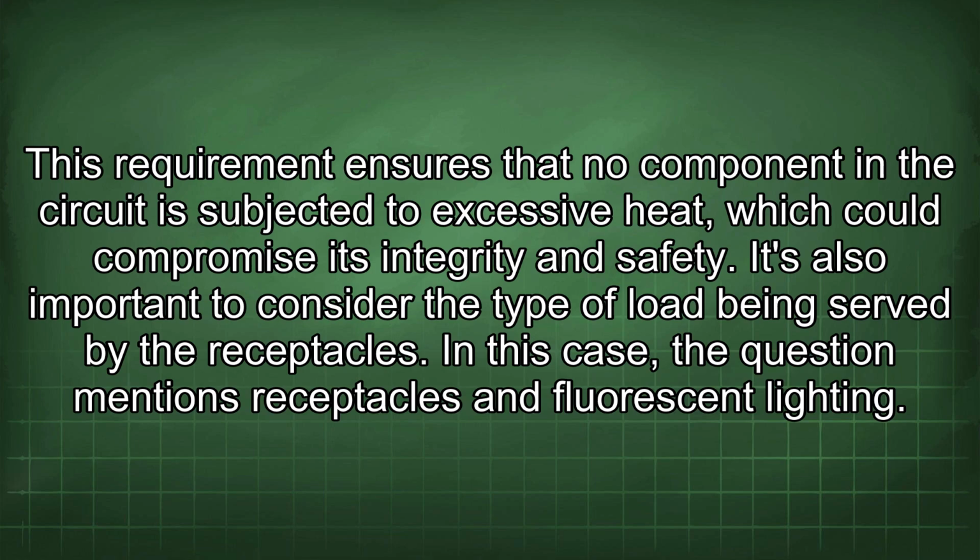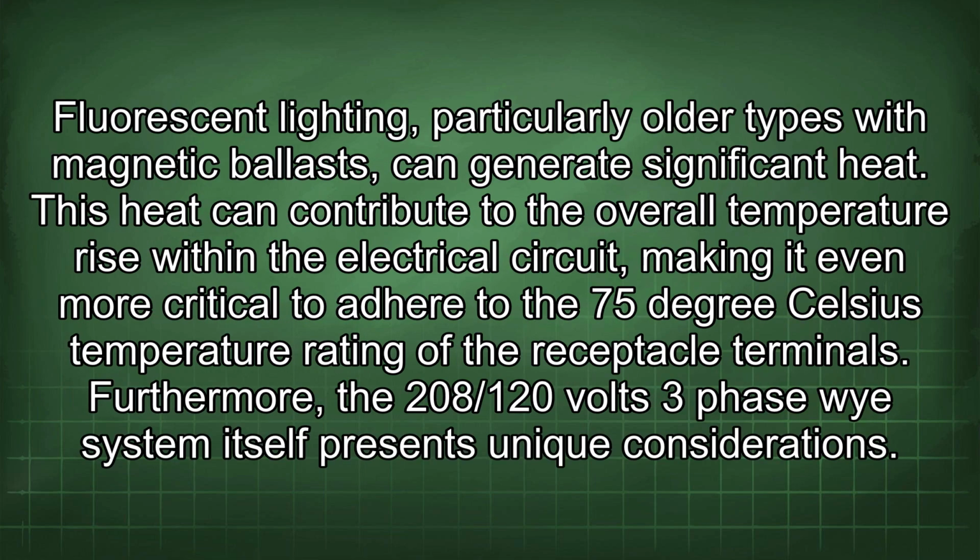In this case, the question mentions receptacles and fluorescent lighting. Fluorescent lighting, particularly older types with magnetic ballast, can generate significant heat. This heat can contribute to the overall temperature rise within the electrical circuit, making it even more critical to adhere to the 75°C temperature rating of the receptacle terminals.